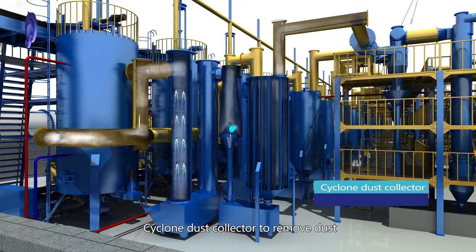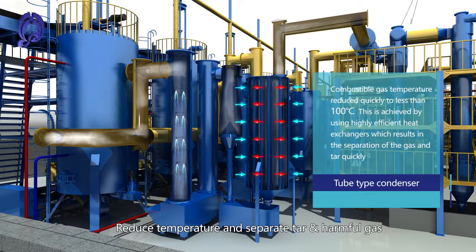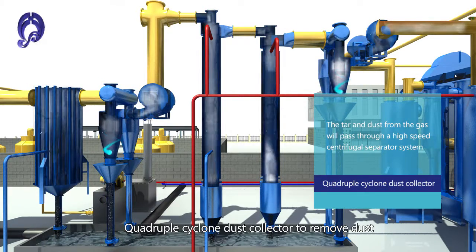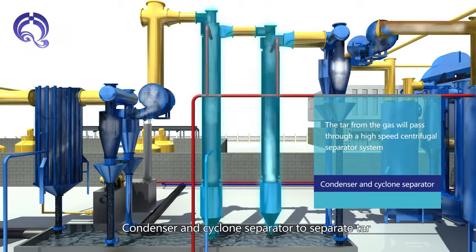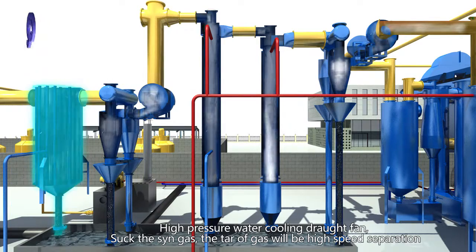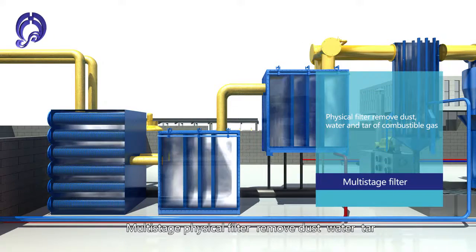A Cyclone Dust Collector removes dust, followed by a Tube-Type Condenser that reduces temperature and separates tar and harmful gas. A Quadruple Cyclone Dust Collector, Condenser and Cyclone Separator further separate tar. A High Pressure Water Cooling Draft Fan draws the syngas, with multi-stage physical filters removing dust, water, and tar.